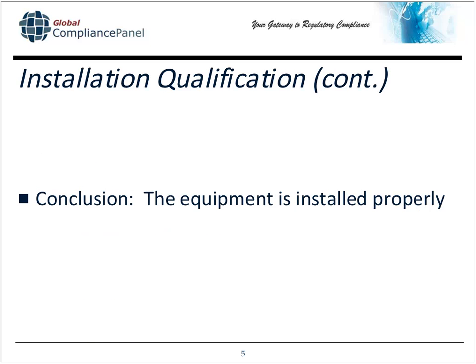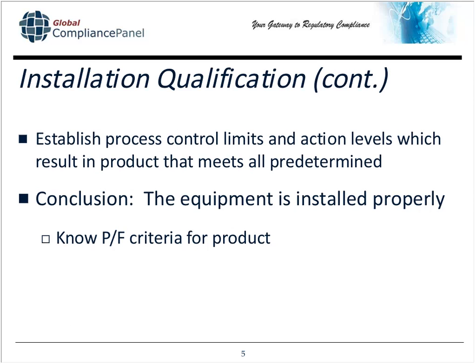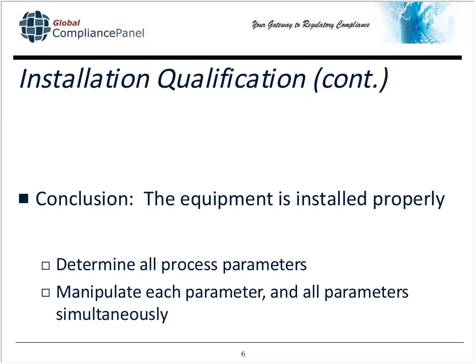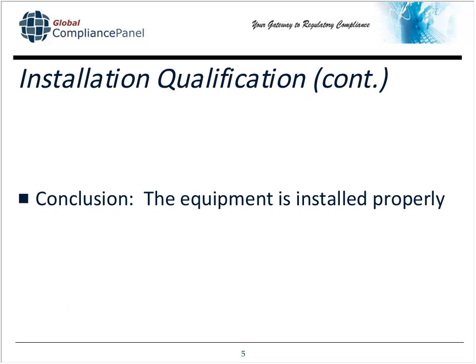The conclusion of the installation qualification, because you want to make sure with your IQ, your OQ, we'll define those a little later, and PQ, everything has a conclusion to it. And the conclusion to the IQ is, yeah, I have accounted for every implication when it comes to how this piece of equipment is installed, and this equipment is installed properly. At the end of the PQ, we're going to have a sign-off document that contains all of the requirements of the IQ with signatures at the end.